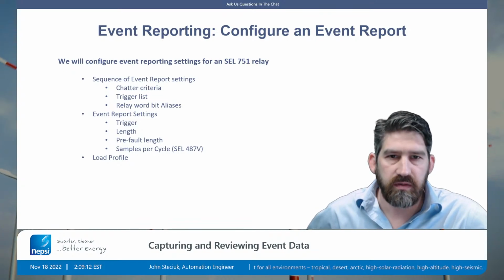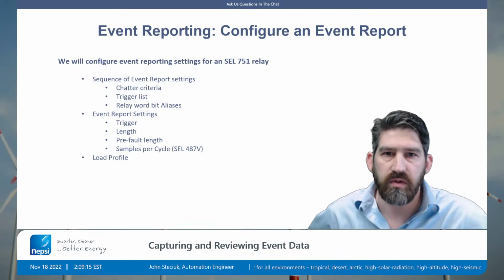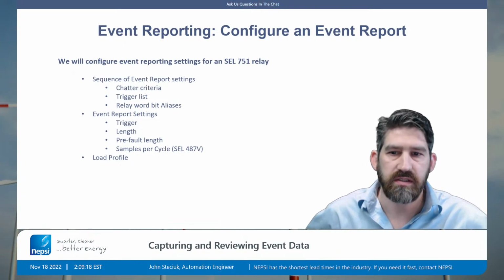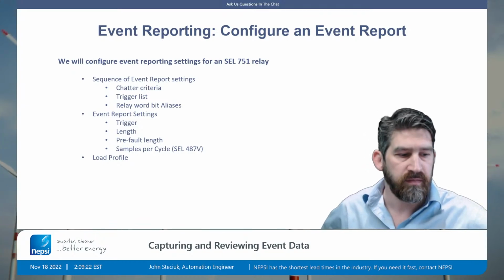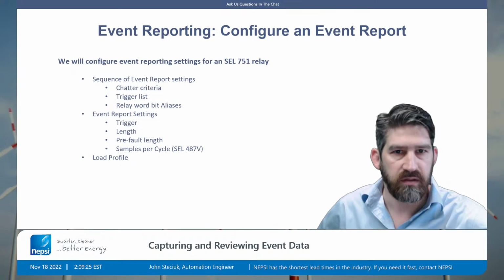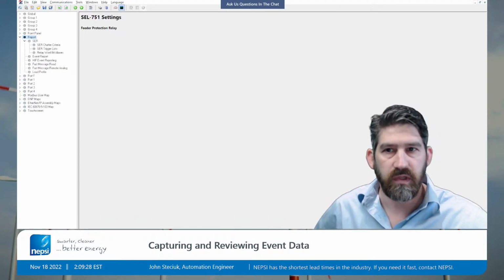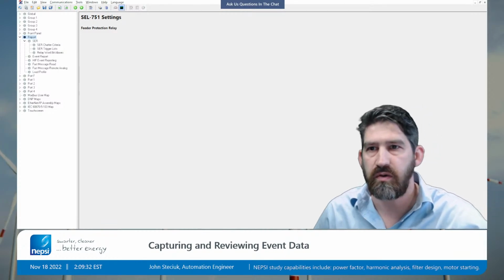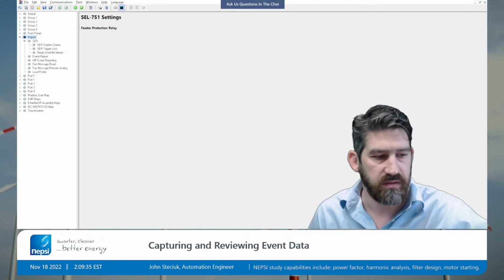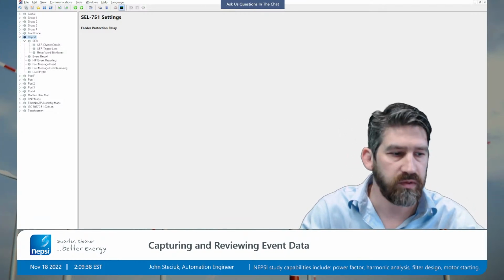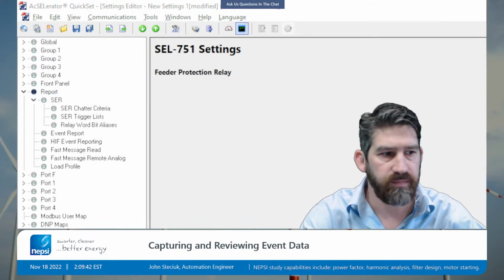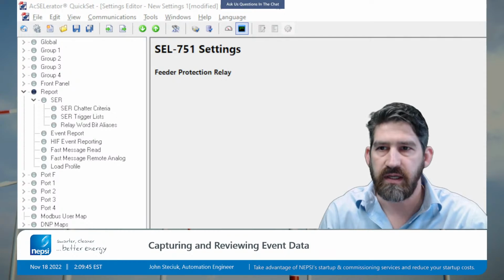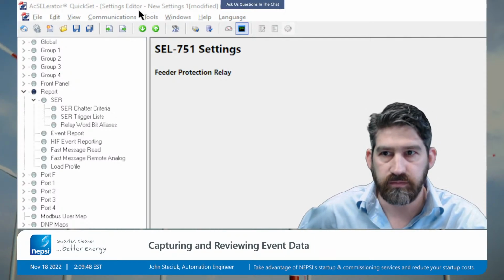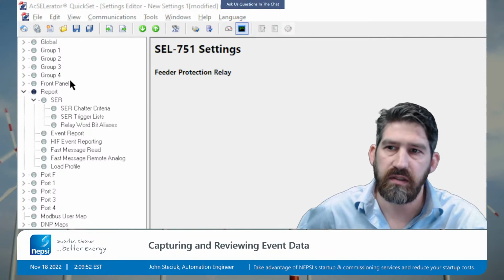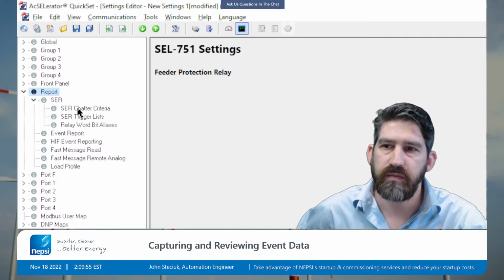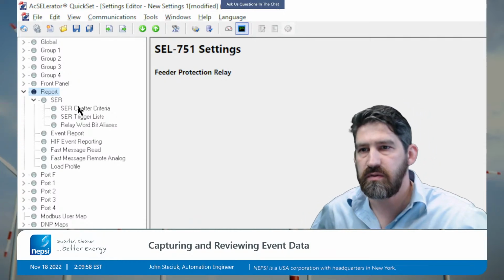Alright, so what I want to do now is take you through the configuration of an event report and sequence of event report settings, and take a look at load profile settings for an SEL 751 relay. So to do that, I'm using this AcSELerator QuickSet software, which is Schweitzer's setting software. I'm going to be zooming in from time to time so that it's more clear what I'm doing here. But I'm connected to this 751 relay, and looking at the report settings under SER for sequence of events.